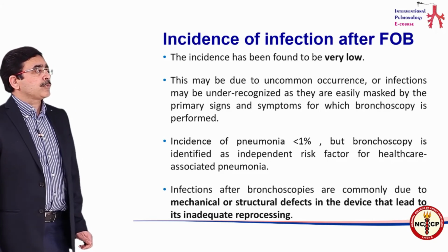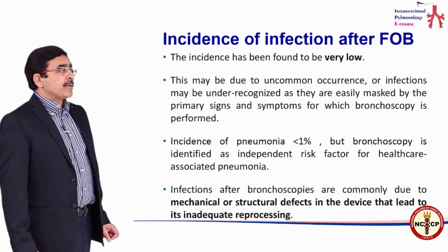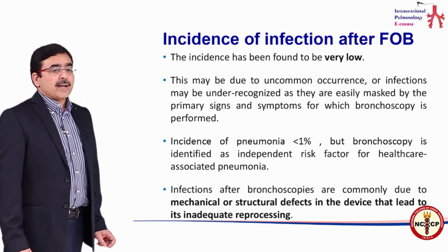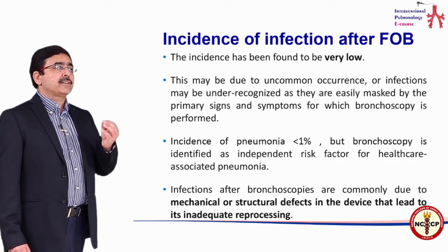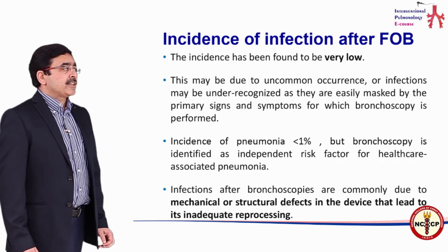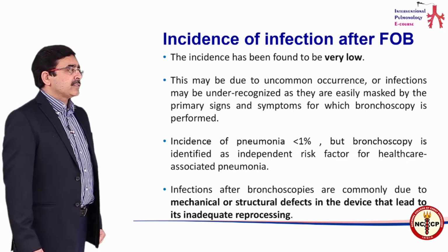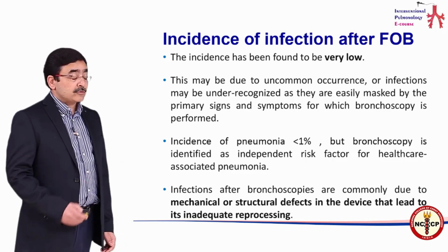Infections after bronchoscopies are most commonly due to mechanical or structural defects in the device that lead to inadequate reprocessing. If there is a tear or a leak in the channel, that tends to accumulate a lot of bacteria, which can be given to the next patient.